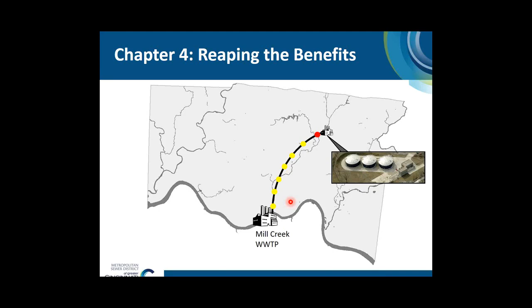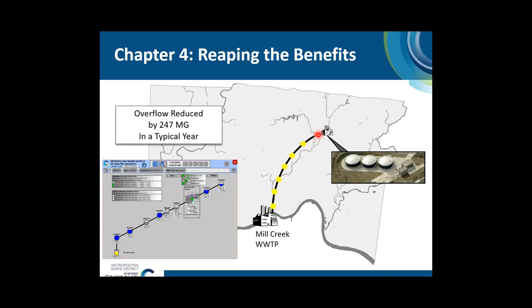We pulled that into our SCADA system, and since the SCADA system now sees data from these downstream manholes, the facility can alter its operations automatically, without operator intervention, to take more flow into the facility and treat it as necessary—meaning less flow goes down and clogs the interceptor. This has been shown to save us over 247 million gallons of combined sewer overflow in a typical year, on top of its original purpose of keeping this manhole from overflowing.